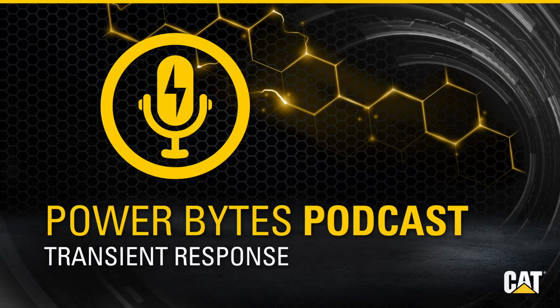What this means is that you may have two generators with the exact same power rating, but because one has a higher BMEP rating, it might take more steps per the standard to get to the full power. This often is overlooked or misunderstood in specifications when customers request generators meet a specific performance category.